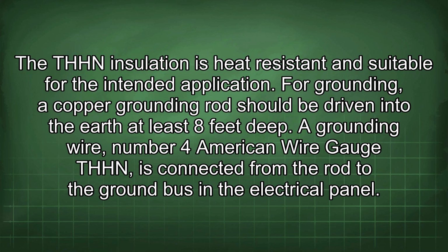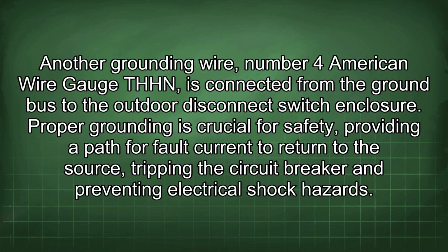For grounding, a copper grounding rod should be driven into the earth at least 8 feet deep. A grounding wire, number 4 American wire gauge THHN, is connected from the rod to the ground bus in the electrical panel. Another grounding wire, number 4 American wire gauge THHN, is connected from the ground bus to the outdoor disconnect switch enclosure. Proper grounding is crucial for safety, providing a path for fault current to return to the source, tripping the circuit breaker and preventing electrical shock hazards.